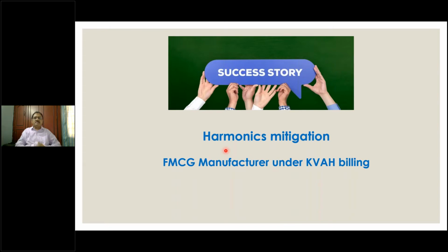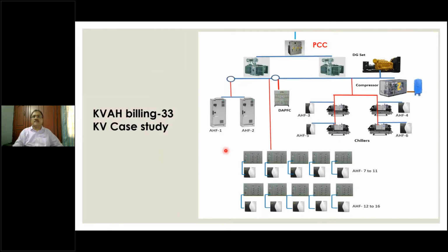So this is an FMCG manufacturer in Andhra Pradesh where there is kVAH billing. What we did, this is the solution topography or solution architecture. They had a point of common coupling 33 kV incomer, 2 transformers, and then the main panel. This was the 433 volt bus. It was going to 10 workstations or MCCs, motor control centers, 10 numbers in the shop floor. And they had 4 chillers. They had a DG set and a compressor also, common header.